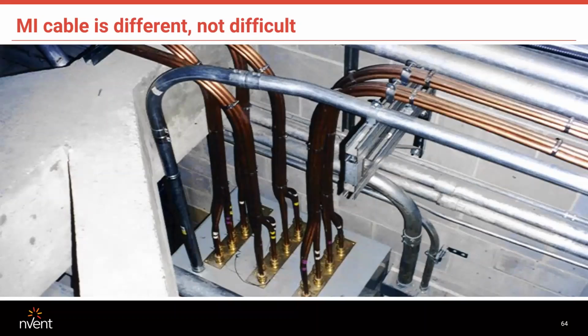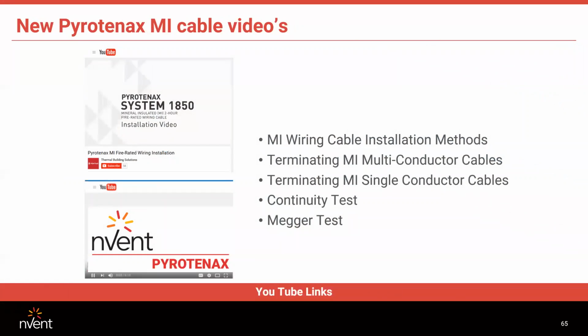And again, when you have bundles of cable, if the free air rating is used, you want to keep the spacing 2.14 cable OD diameters between bundles. So for example, if you're working with our 500 kcmil, which has an OD of 1 inch, and two bundles, the A, B, C, neutral, or whatever, are running adjacent to one another, you want them to be slightly over 2 inches apart from each other, if the free air rating is being used. On our website, we have pretty much all the information you need for installation, for doing megger testing and whatnot.